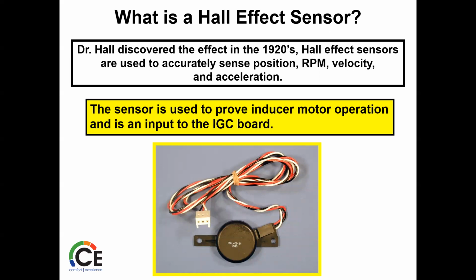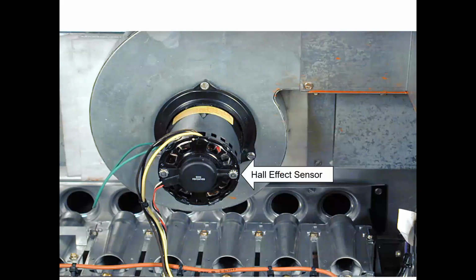The Hall effect sensor has been around for a long time, as you can see there. It's a love-hate thing. Some guys are okay with it. Some guys hate it. It's basically just a magnetic switch that's monitoring the RPMs of that motor. It's supposed to prove that it's working. So you can see it here on the back of a motor. It's got a little magnet in there that it turns as the motor windings turn. And as long as it hits its rotation in the right amount of time, everything's happy-dory, right? So once that's verified, just like in a residential furnace, then it goes through the rest of the ignition sequence.